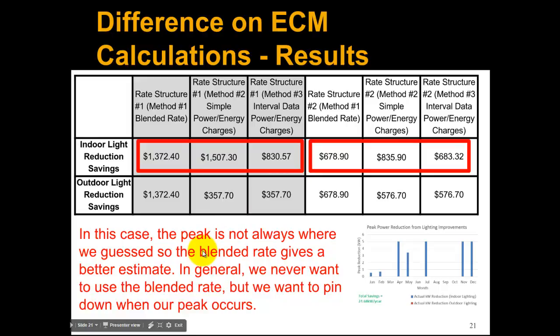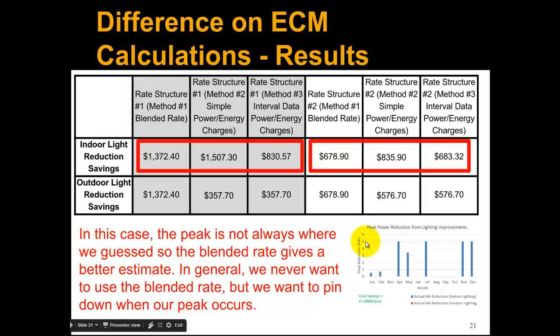In some cases the peak is not always where we guessed it, so the blended rate can actually give a better estimate than method two. We need to be careful that if something occurs just a portion of midday, we probably want to be careful about the estimates we use — and if we have interval data, just take the time to calculate in Excel. In general, if you have interval data, which most buildings do now, go ahead and do the real calculation with the interval data instead of estimating, because that's really going to give you the best estimate of your building cost savings. Thanks for listening.